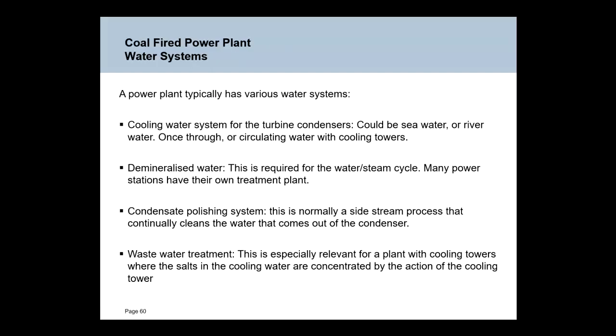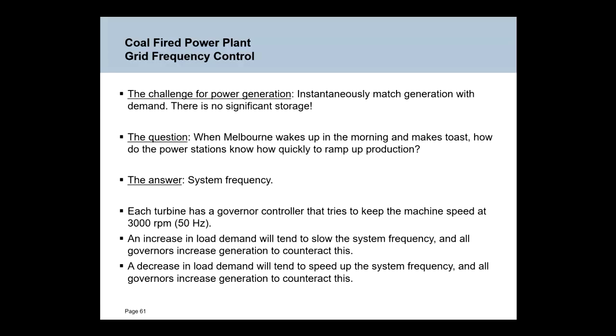Large power plant will also have a significant number of water systems. So some very important people in coal and gas-fired power plants are the chemists who manage all of the water systems. There will be a cooling water system for the turbine condensers, a demineralized water system to produce water that goes around that steam cycle, and that water has to be very, very pure. A condensate polishing system that cleans up that water if it gets dirty for some reason, and a wastewater treatment system to treat any of the wastewater, particularly from the cooling water system. Okay, all these things very important and quite complex to manage in a power station.